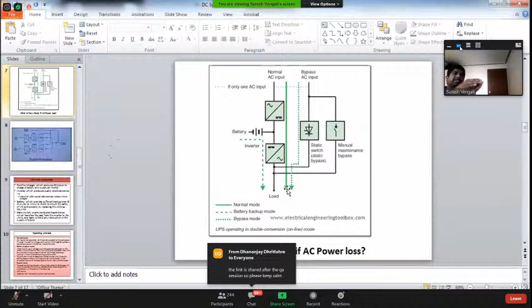We faced the same problem two days back - the vendor, I don't know, forgot or something, and didn't connect that earth link. The protective earthing wasn't connected, only neutral was connected, and they forgot. So we opened the drawing and verified it, and found some systems had a TNC system, and some didn't - some were TNC and some were TNS systems.